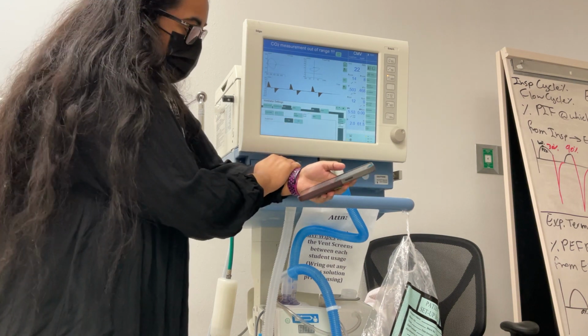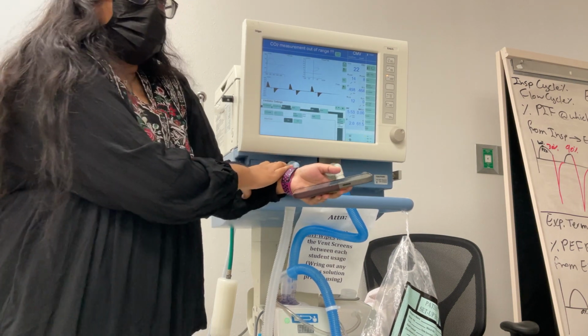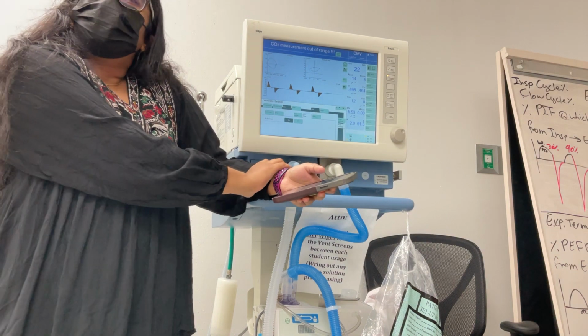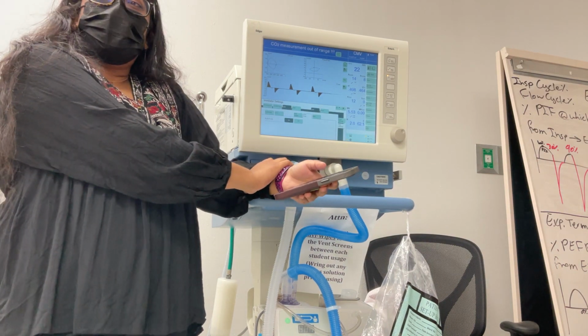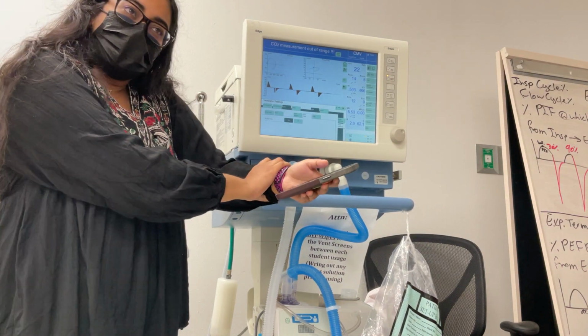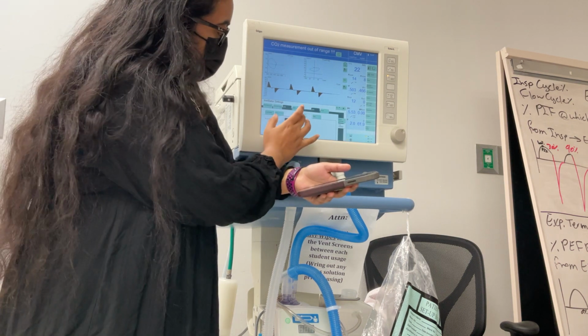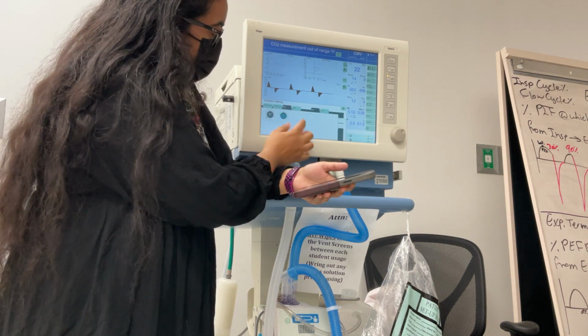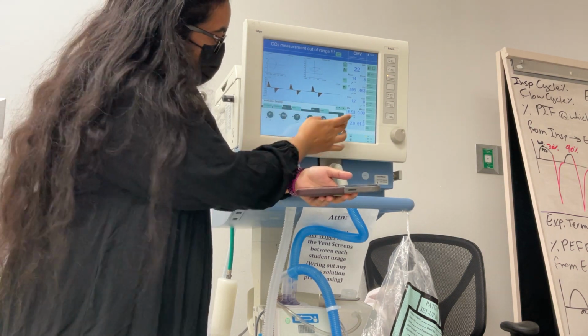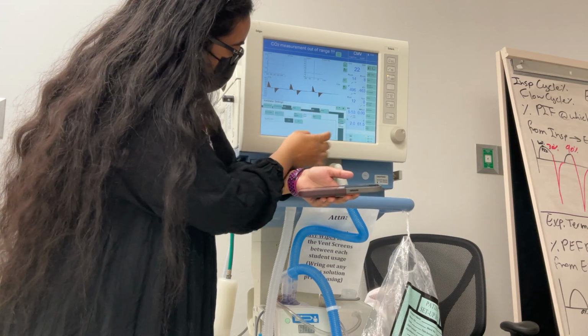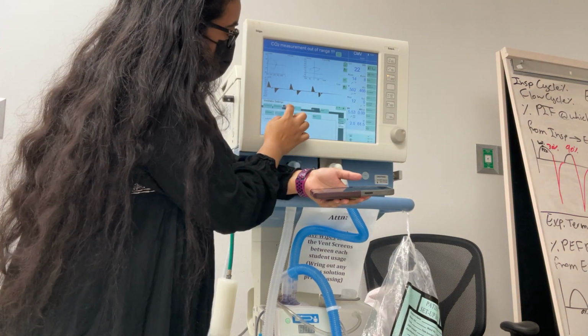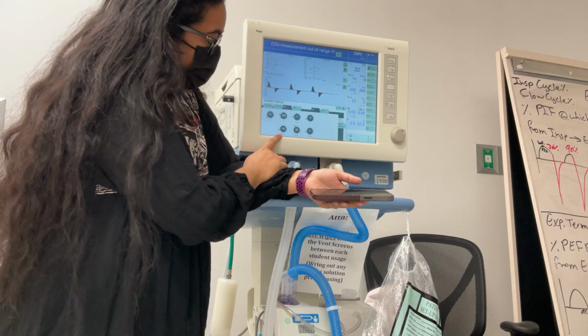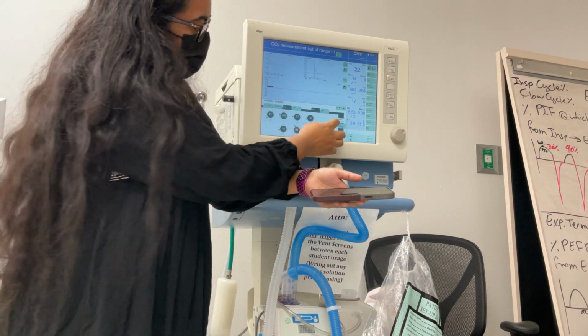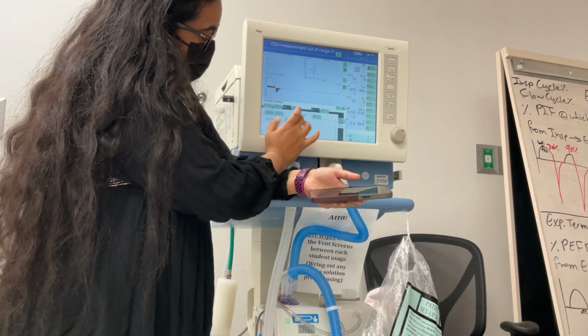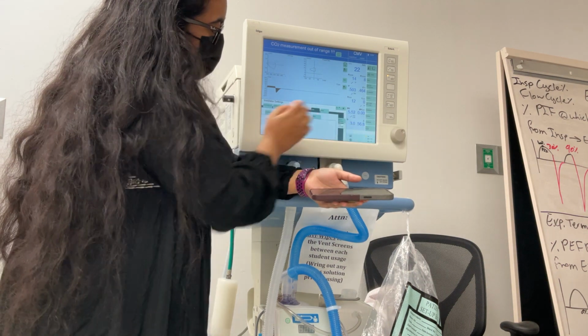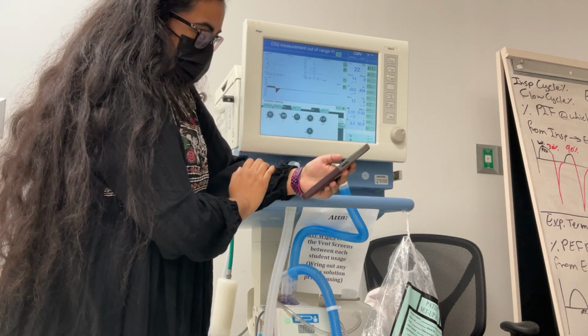Next you have auto flow. What happens when you turn auto flow on? So it'll make your volume modes into PRVC. And if you turn it on, so we'll go back to the mode itself, you'll see auto flow is on right now. We turn it off. If we go back, you can actually adjust your flow rate here. If you turn it on, you cannot because it's auto flow. So that goes away there.